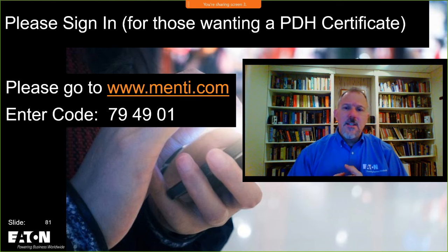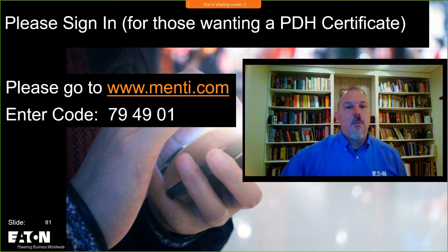UL 489 does not require it. You've got to come to my circuit breaker basics class, which I'm going to have next week. I haven't put the notice out for that. I believe it's going to be on Thursday afternoon. It's not going to be 12 to 2, but I'm going to see if I can make it 12 to 2. That one's still out there. But you have to understand molded case circuit breakers to really understand why you can't rely on that thing to give you arcing fault detection.